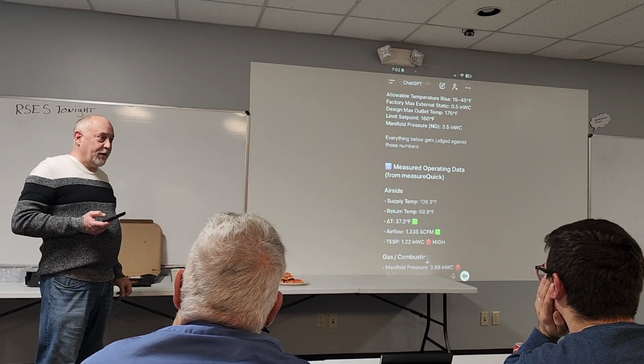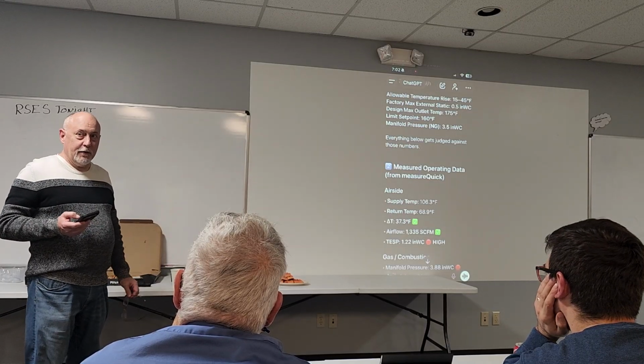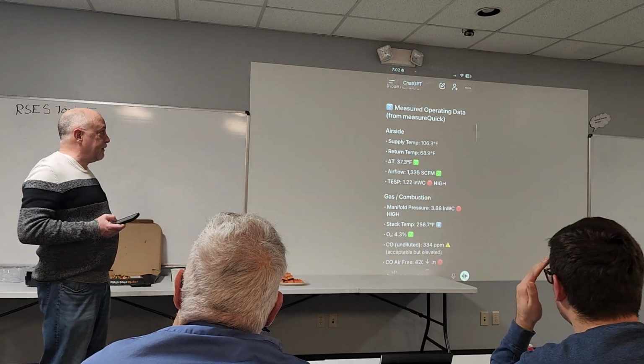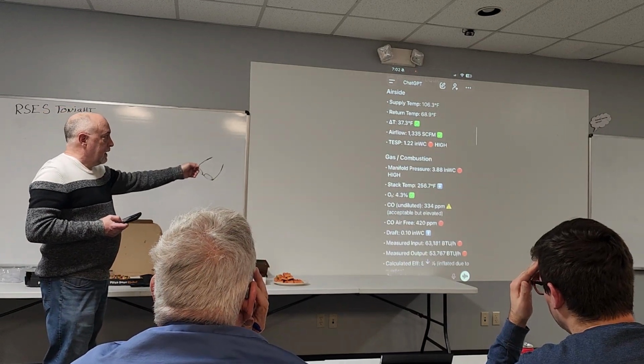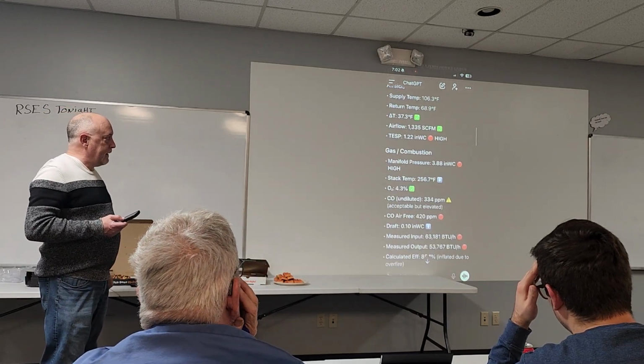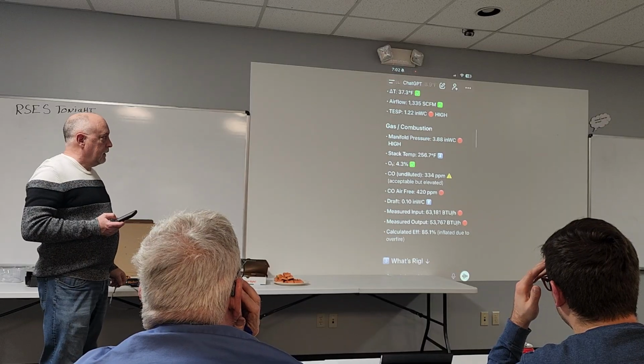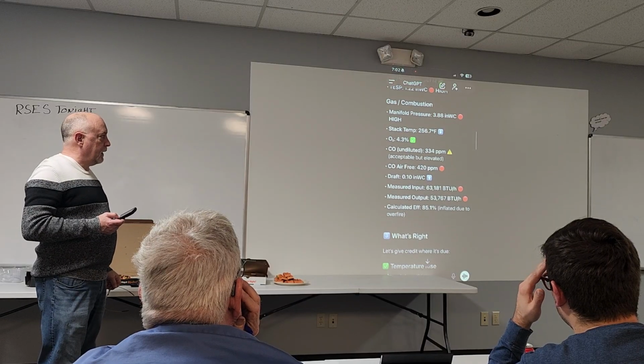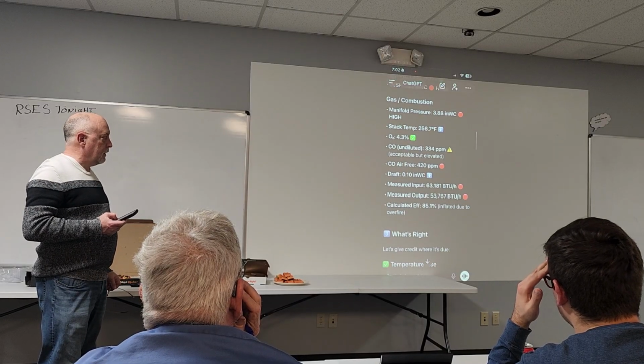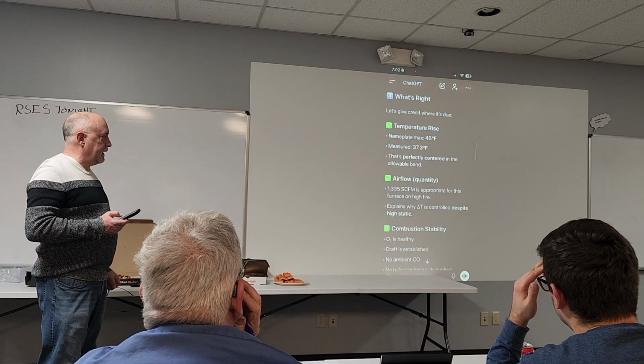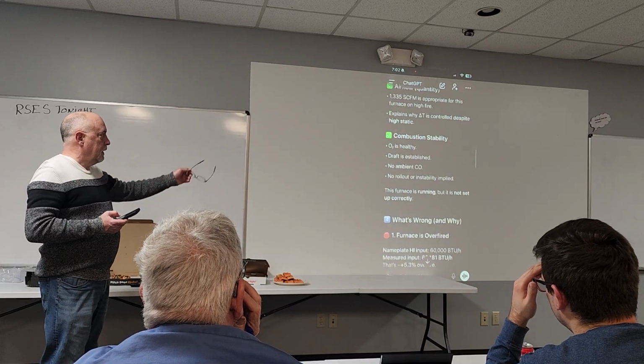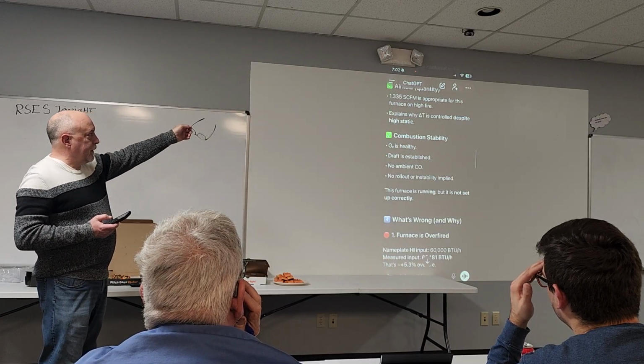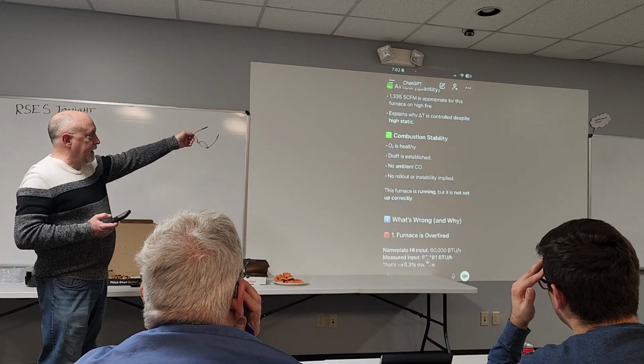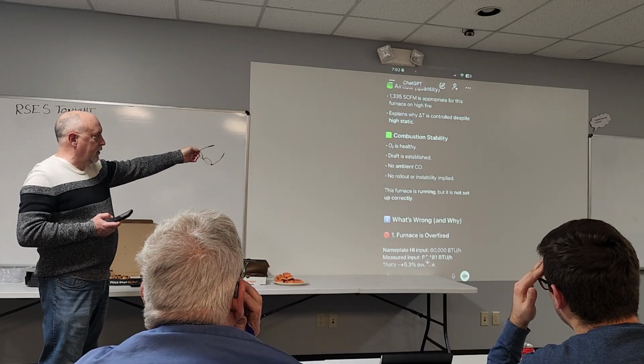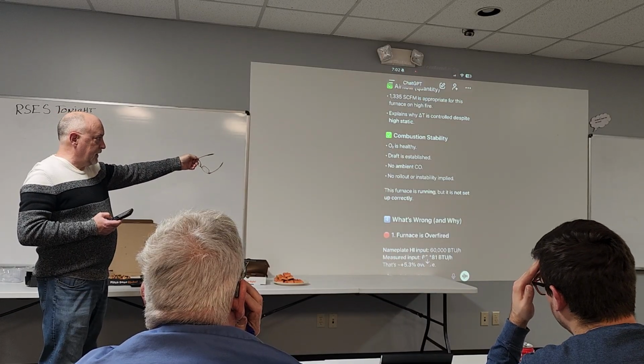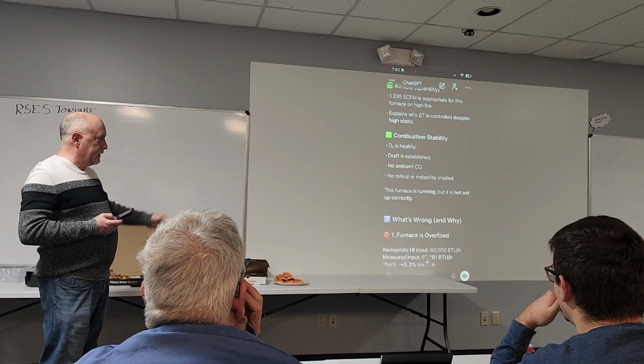This furnace could have a 5-ton drive on it. I don't know how Goodman came up with a 15 to 45 degree rise. Combustion: manifold pressure is high, stack temperature is low, undiluted CO air free. All right, so the airflow is appropriate, which explains the delta T in spite of the high static. The O2 is healthy, draft is established, no CO, no ambient CO, no rollout or instability.